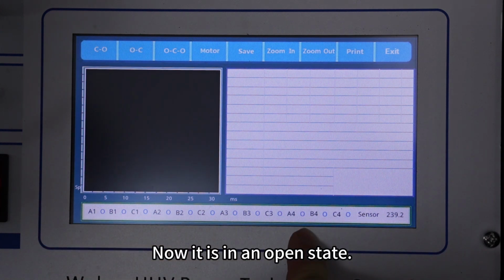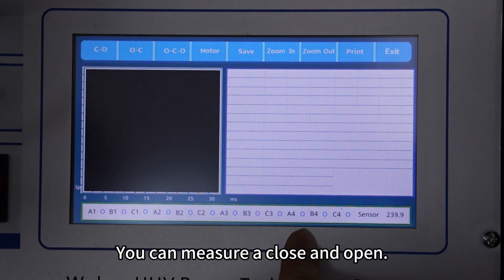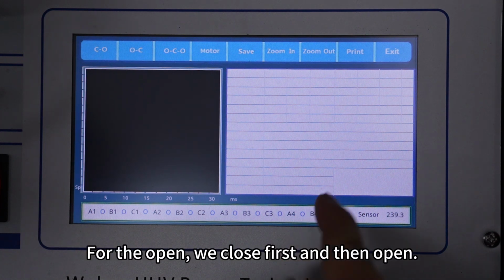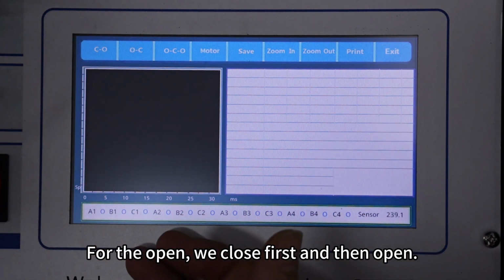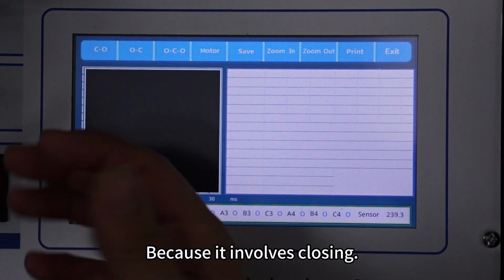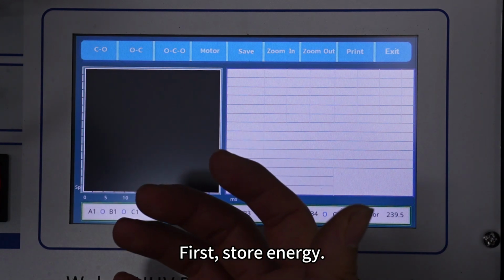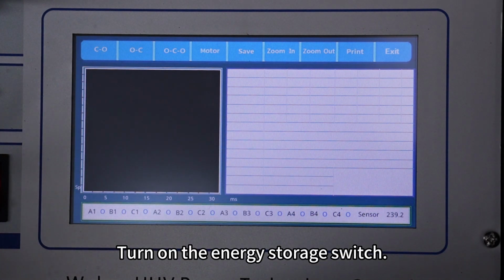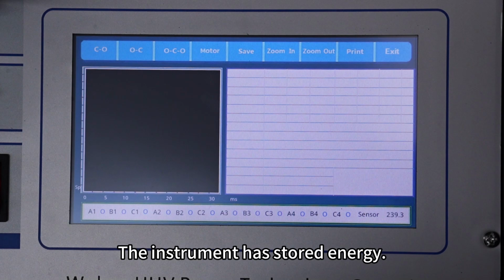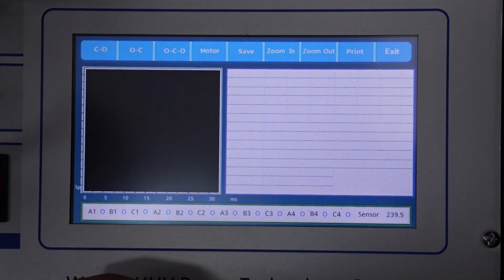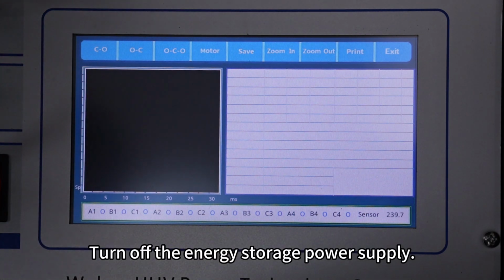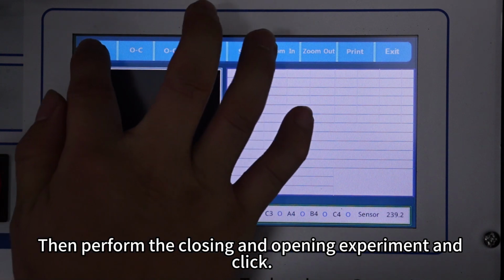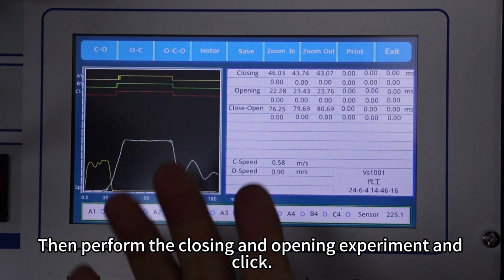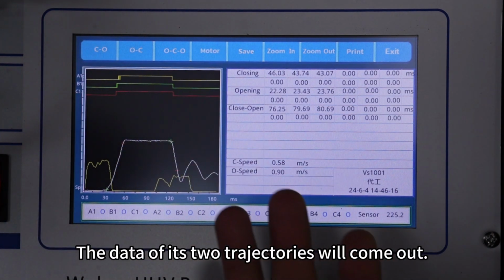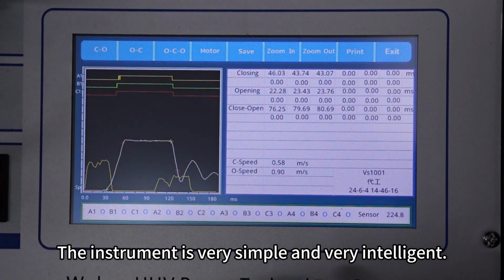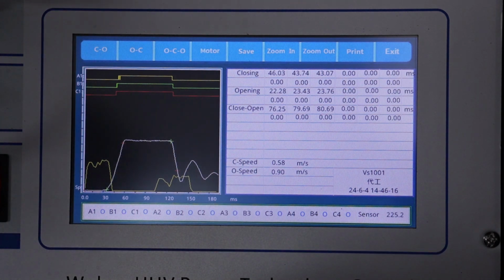Now it is in an open state. You can measure close and open. For the open, we close first and then open. Because it involves closing, first store energy. Turn on the energy storage switch. The instrument has stored energy. Turn off the energy storage power supply. Then perform the closing and opening experiment and click. The data of its two trajectories will come out. The instrument is very simple and very intelligent. Exit now.